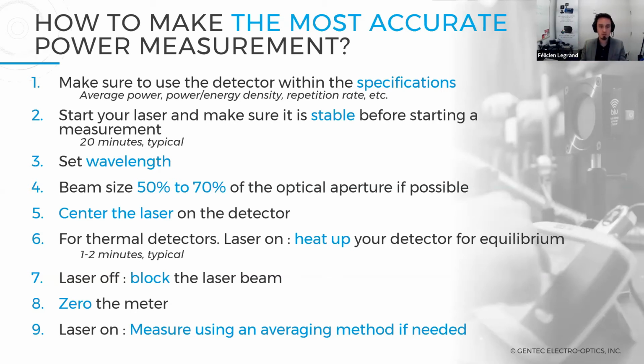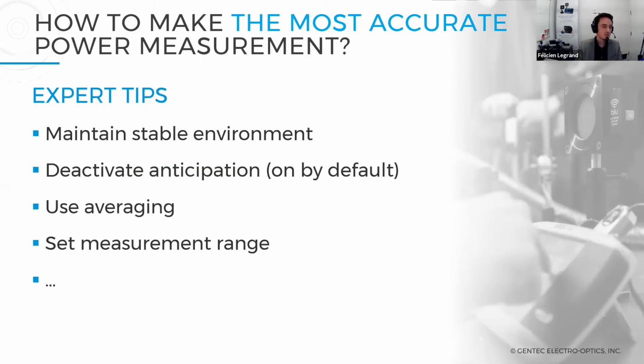Zeroing the meter is to subtract the background, to be sure that any heat sources or any reading that is not exactly zero is removed. Then, with your laser back on, you could use an averaging method, for example, to smooth out the reading of the laser power. All right, some tips: it's really important for thermal detectors to have a stable environment in terms of heat fluctuations. Otherwise, for low power, you could use a photodiode, which is more flexible for these things.